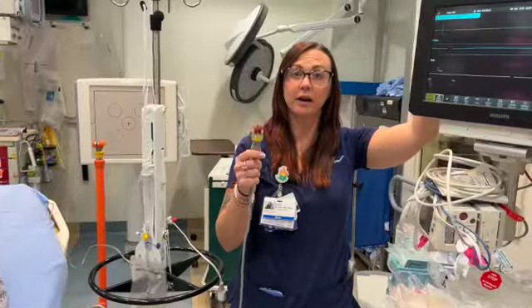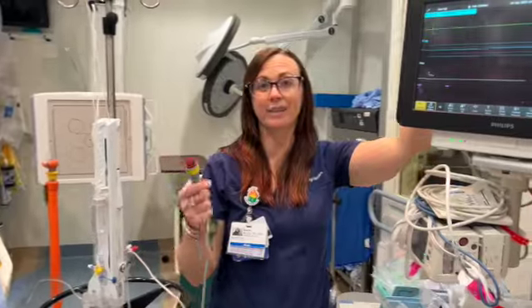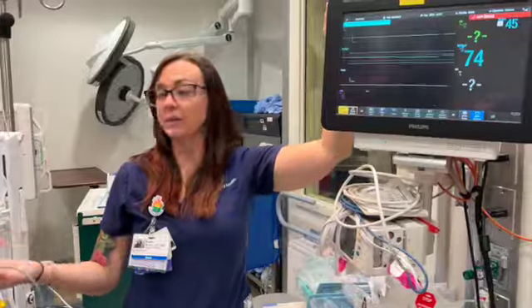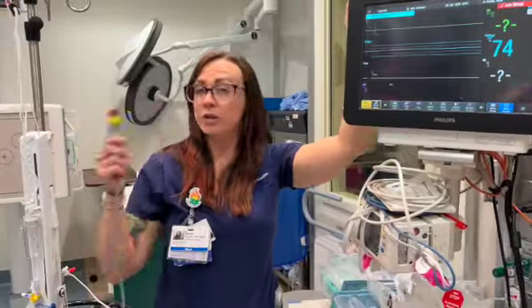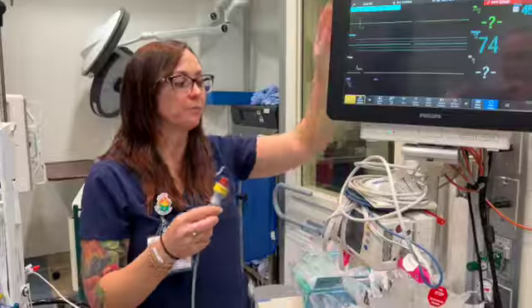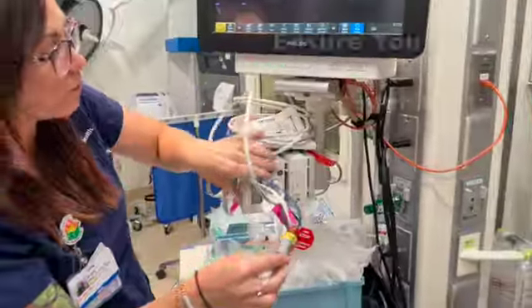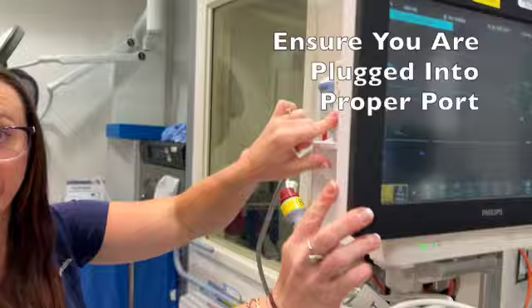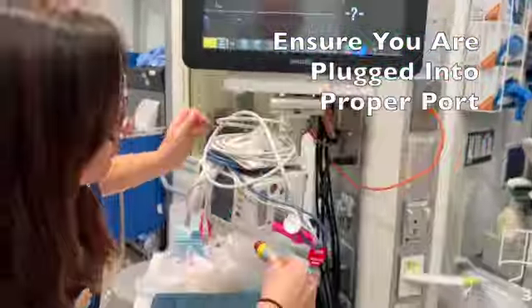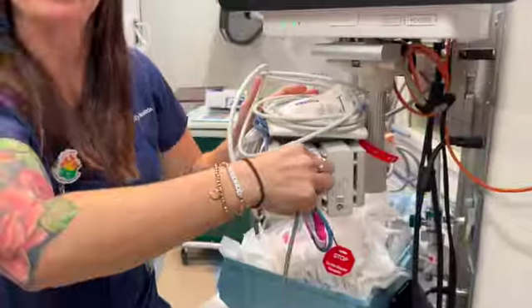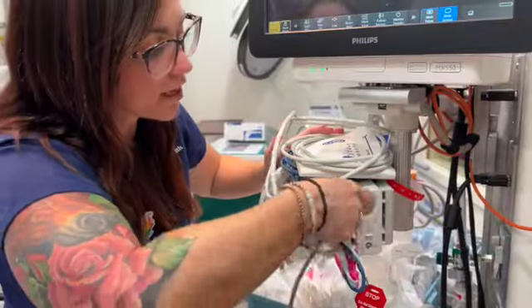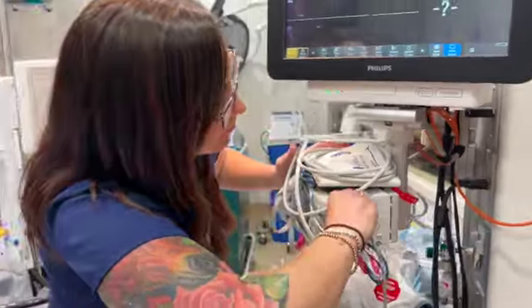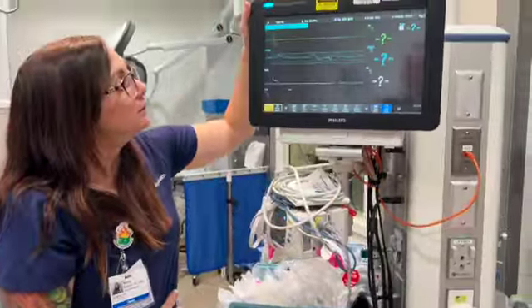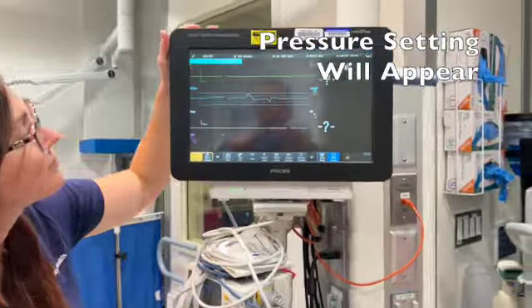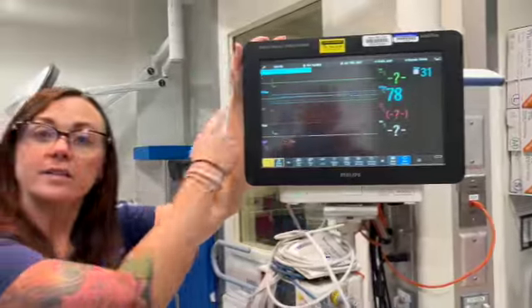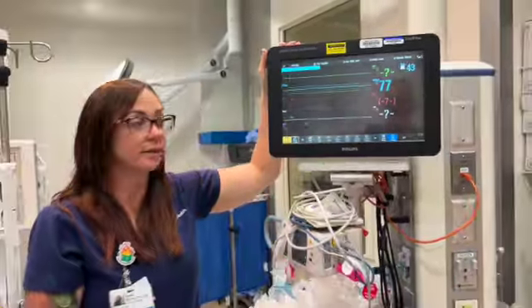Next, we're going to plug our pressure cable into our monitor. Typically, these types of procedures happen in the trauma room. In order to do this correctly in our trauma room, make sure that you're plugging this cable into the bottom monitor and not the top here. This is going to just be gently inserted where it says press for pressure. And from there, you'll see the pressure come up onto the screen.